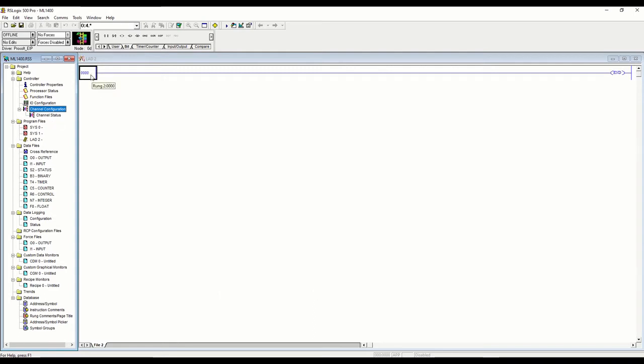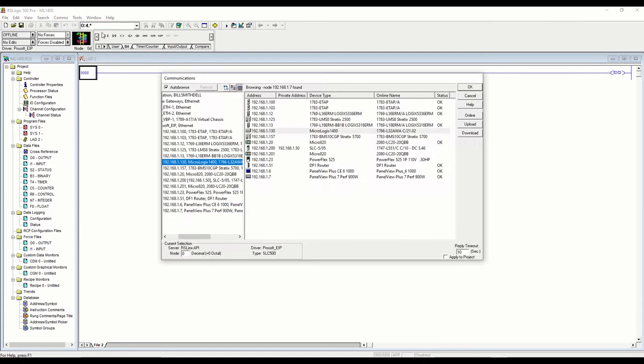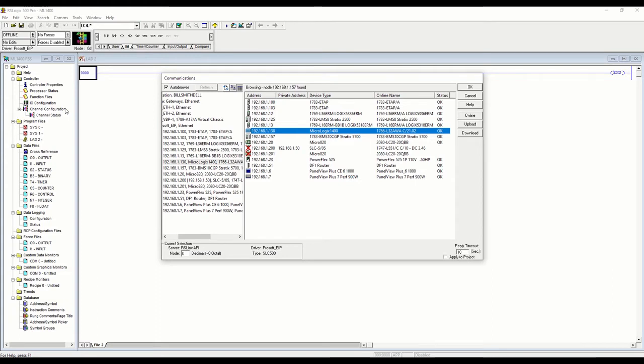Now the next step — it's not strictly necessary but I like to get it out of the way — is to go ahead and download to the controller. The reason for that is when we enable that Modbus functionality on the ethernet port, it's going to require a reboot on the controller for that to take hold. I like to get that out of the way so I can handle programming, uploading, and downloading without having to restart again. It's a preference — you can wait and do one massive download, but I prefer to get it done early.